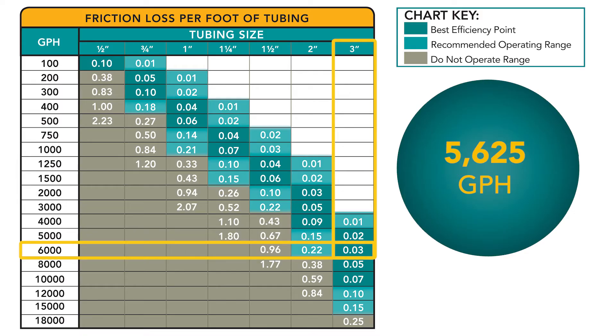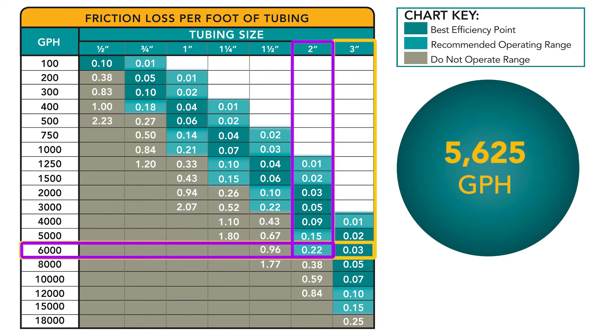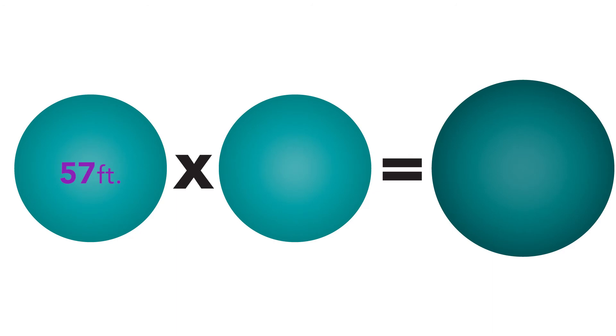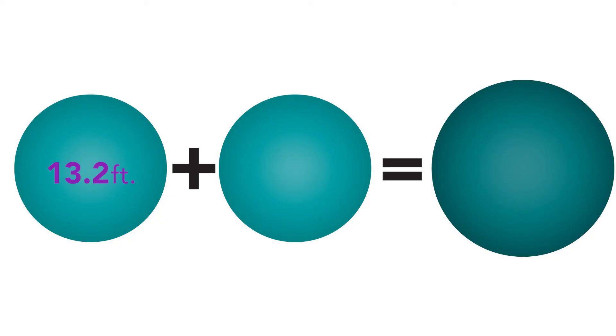This is why tubing size is so important. If you have 2-inch tubing instead of 3-inch, the multiplier jumps to 0.22 — over 7 times higher. Through 2-inch tubing, our fitting equivalent lengths also change: we add 8.5, 4.5, and 19 for the 2-inch diameter fittings, giving 57 feet of equivalent length. Multiplying 57 feet by 0.22 gives 13 feet of friction head. Adding that to our 10 feet of vertical head, our TDH would be about 23 feet.